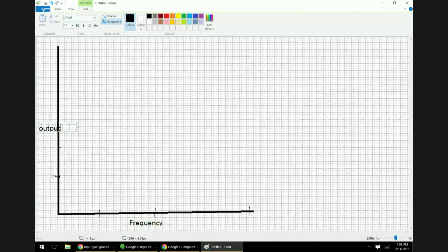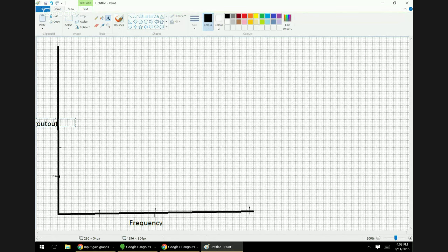now when would we see a graph like that? Not very often, actually. But frequency output graphs are usually used to show the OSPL 90 of the hearing aid. So what does one of them look like? You're used to looking at frequency gain graphs, aren't you? Again, if you know the input, then a frequency output graph you can calculate. It's relatively straightforward.